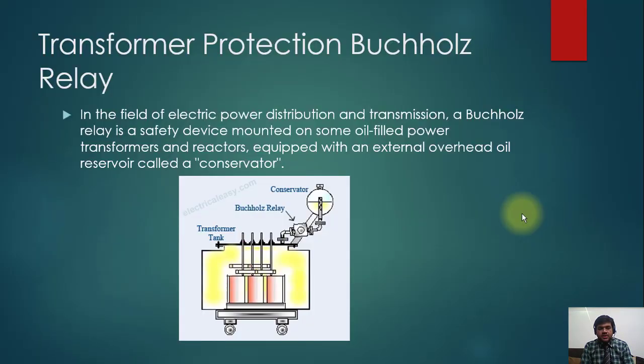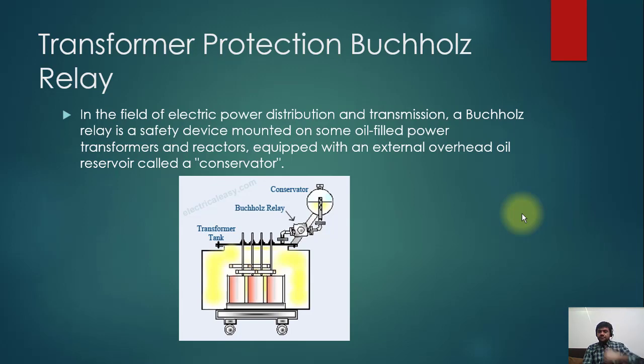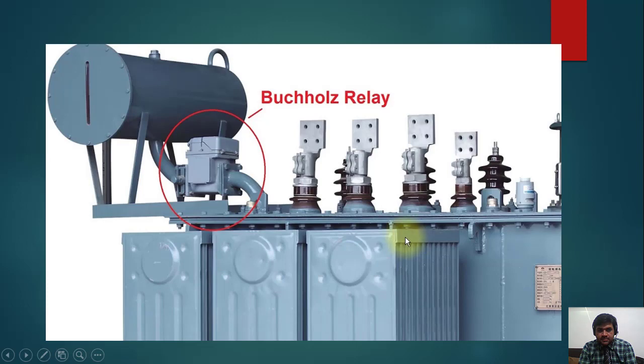Welcome back. We will now discuss another topic: transformer protection — the Buchholz relay. In the field of electrical power distribution and transmission, a Buchholz relay is a safety device mounted on oil-filled power transformers and reactors. The transformer has an external oil reservoir called a conservator. The Buchholz relay is installed between the main tank and the conservator tank.